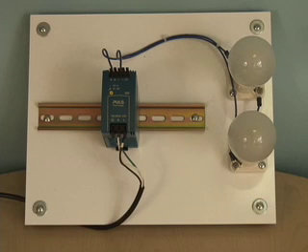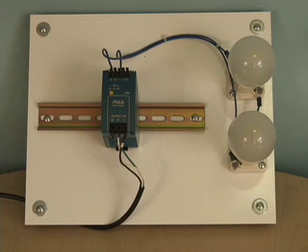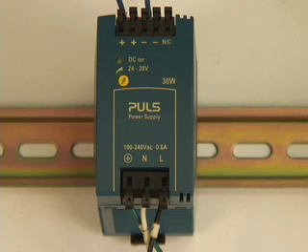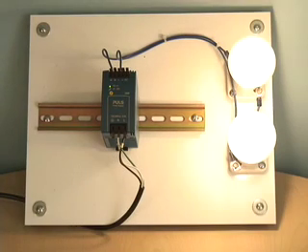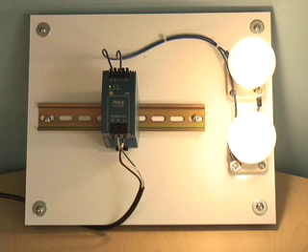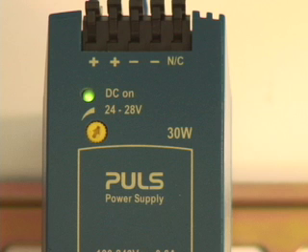To better show the power behind the PULS overload design, we can show this same demonstration utilizing a PULS 30 watt supply. When I plug the unit in, you see that the PULS 30 watt power supply has enough overload capabilities to energize the 50 watt load. And if you look at the DC OK LED, you'll notice that the power supply is still operating within the proper DC output range.